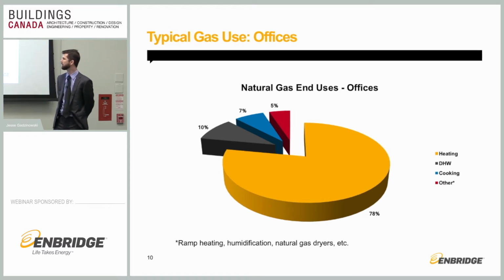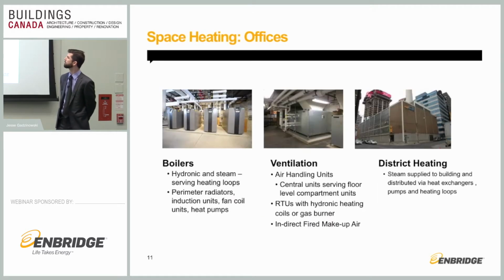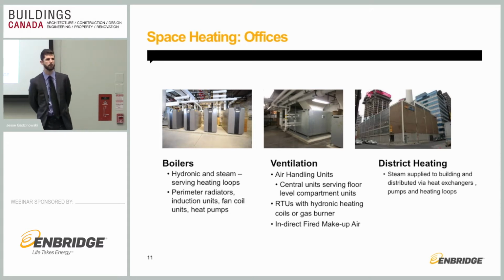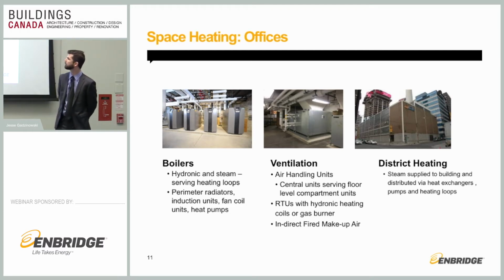Could be ramp heating, humidification, natural gas dryers, things like that. So it's not a very complex thing on the heating side, but there are components that do make it difficult depending on the interactive effects with other systems. Generally, we're finding in large office buildings, boilers, either hydronic or steam, using gas. These systems are serving generally perimeter rads or some perimeter induction units or fan coil units, things like that. Those systems generally will serve the air handling units.